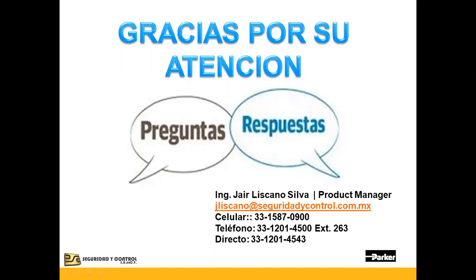Luis Raimundo Ávila pregunta si el producto tiene bus de entrada de corriente directa, o para poder alimentar el drive con corriente alterna o directa. Los equipos muy pequeños no tienen acceso al bus de DC, pero de medianos a más grandes sí tienen las dos terminales del bus positivo y negativo. En un equipo muy pequeño que se quiera alimentar solo en directa, incluso se puede seleccionar un monofásico y alimentarlo desde las líneas, solo utilizaría dos diodos pero trabajaría sin problema.